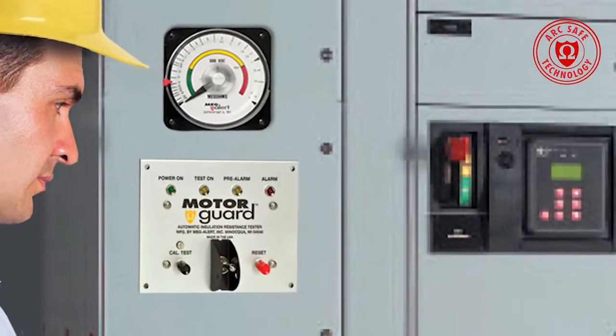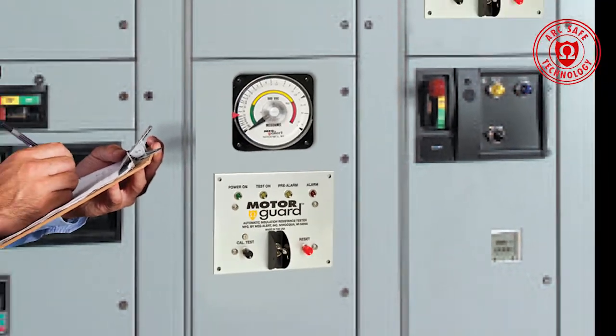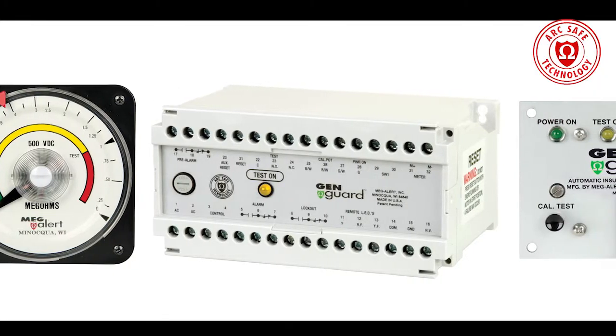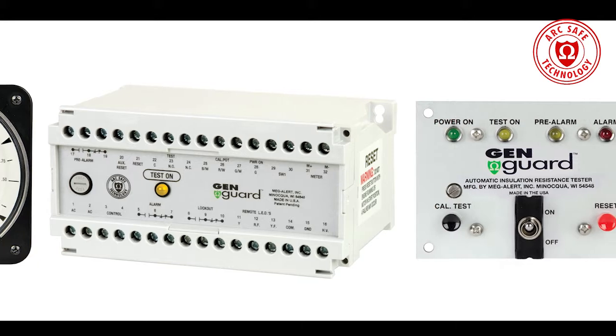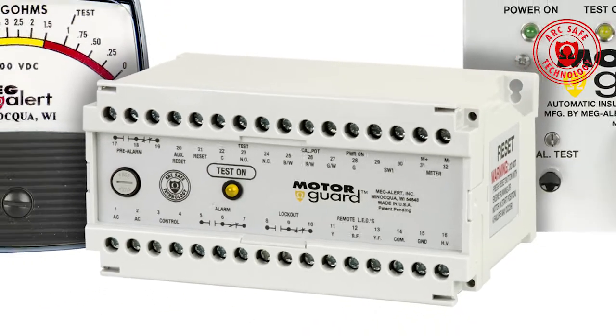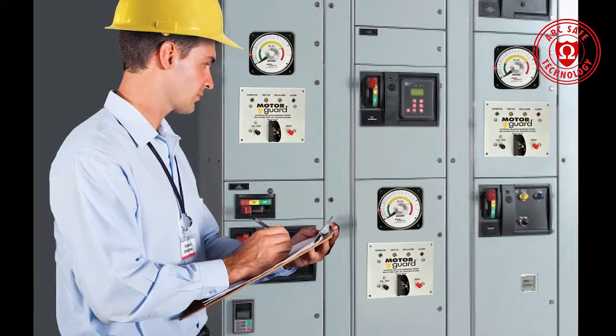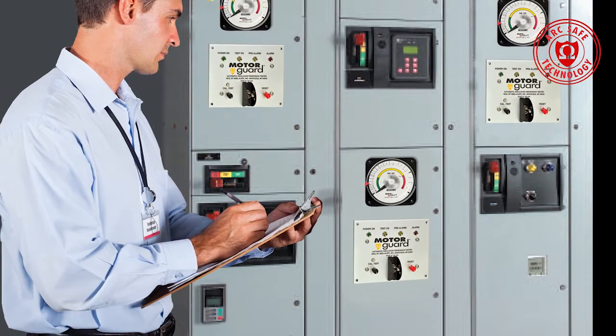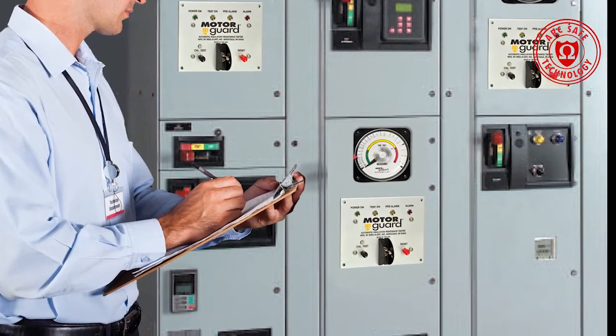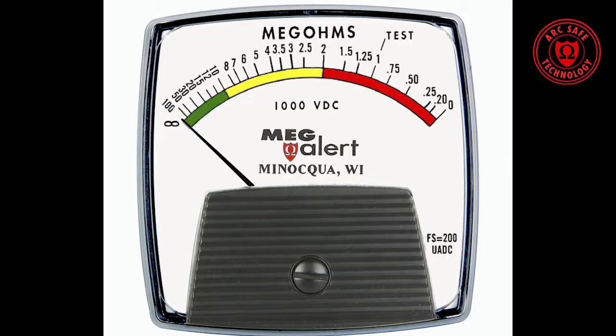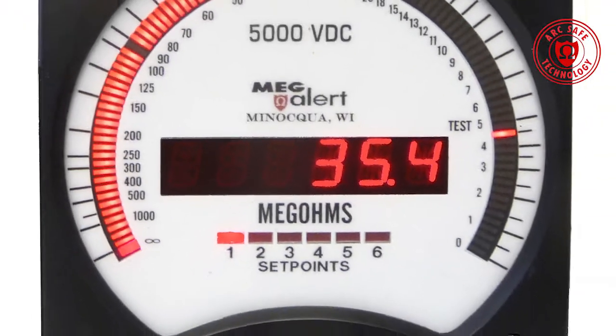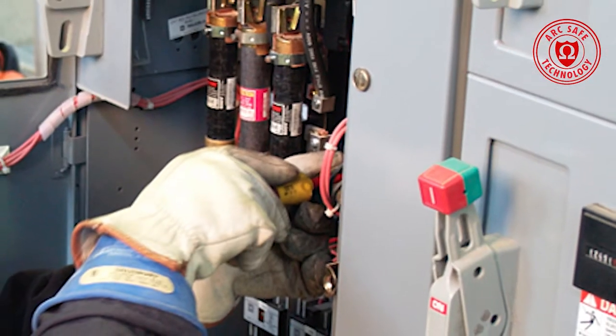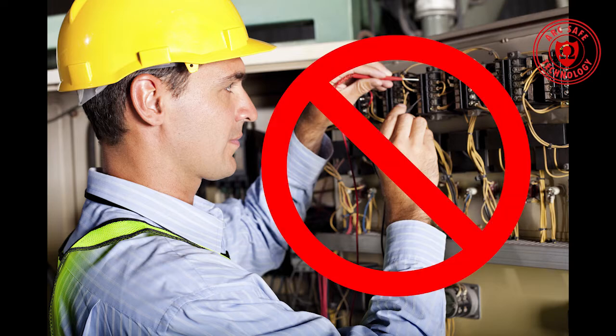The lesser risk is to access control cabinets one time to install a MegAlert system, which then provides continuous testing with no need to continually access the cabinet. By using a continuous, automatic, permanently installed insulation resistance tester and monitor like MegAlert, you will limit the risks involved in doing PM testing and prevent accidents caused by human error and exposure to the inside of the control cabinet.